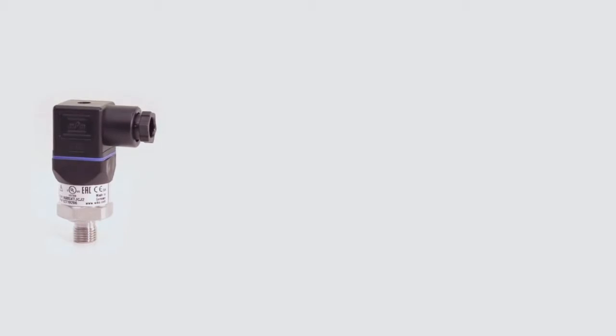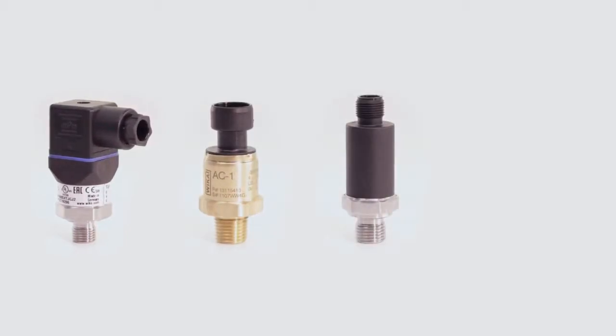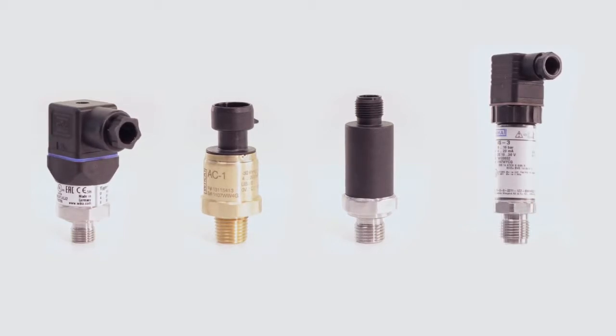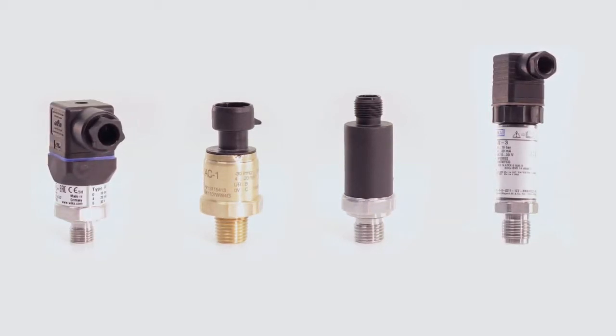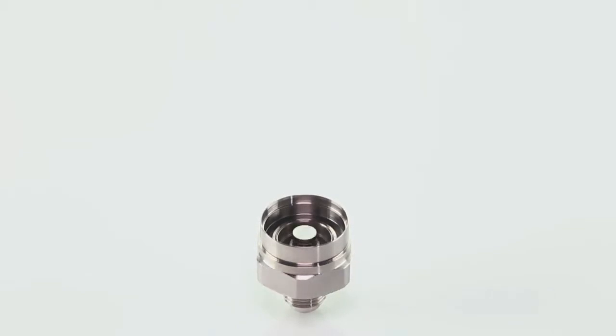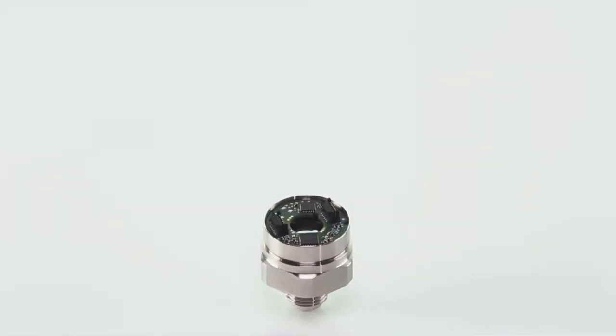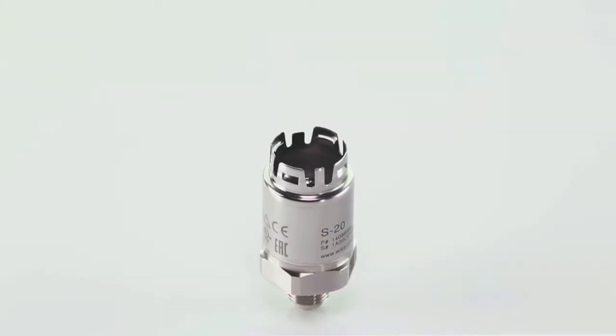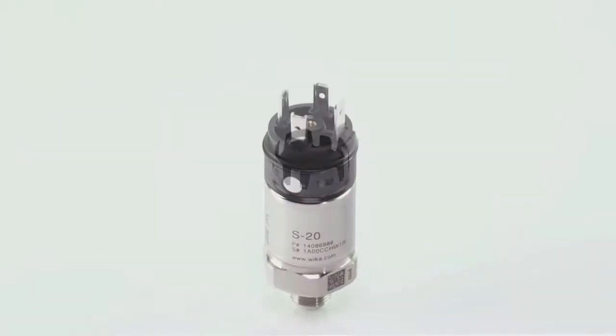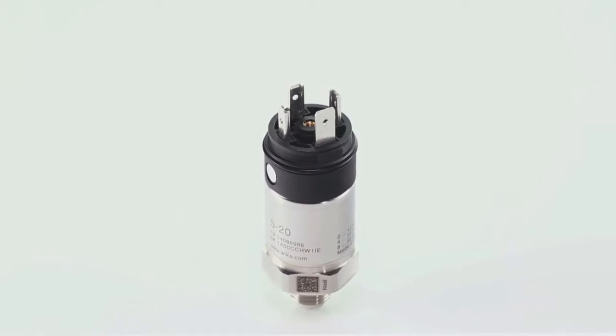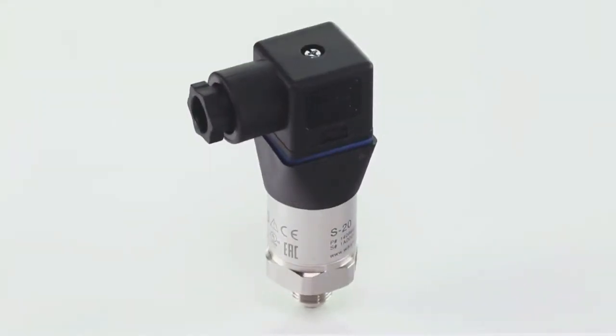Pressure sensors are available in various designs and variants and have proven themselves in multiple industrial applications, even under difficult conditions. Let's take a quick look at the design and function of a pressure sensor. The pressure sensor is screwed into the measuring point at the process connection. The pressure sensor element converts the present pressure into an electrical signal. The downstream electronics amplifies and standardizes this signal. A suitable case protects against environmental influences. The standardized signal is transmitted to the following signal evaluation via the electrical connection.